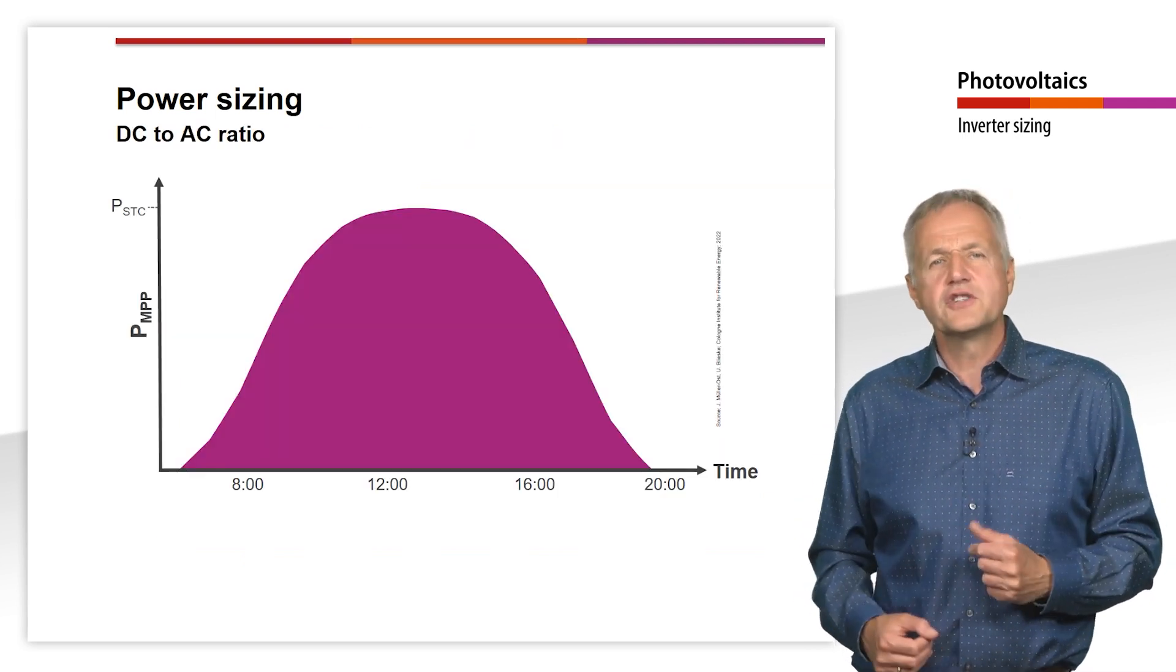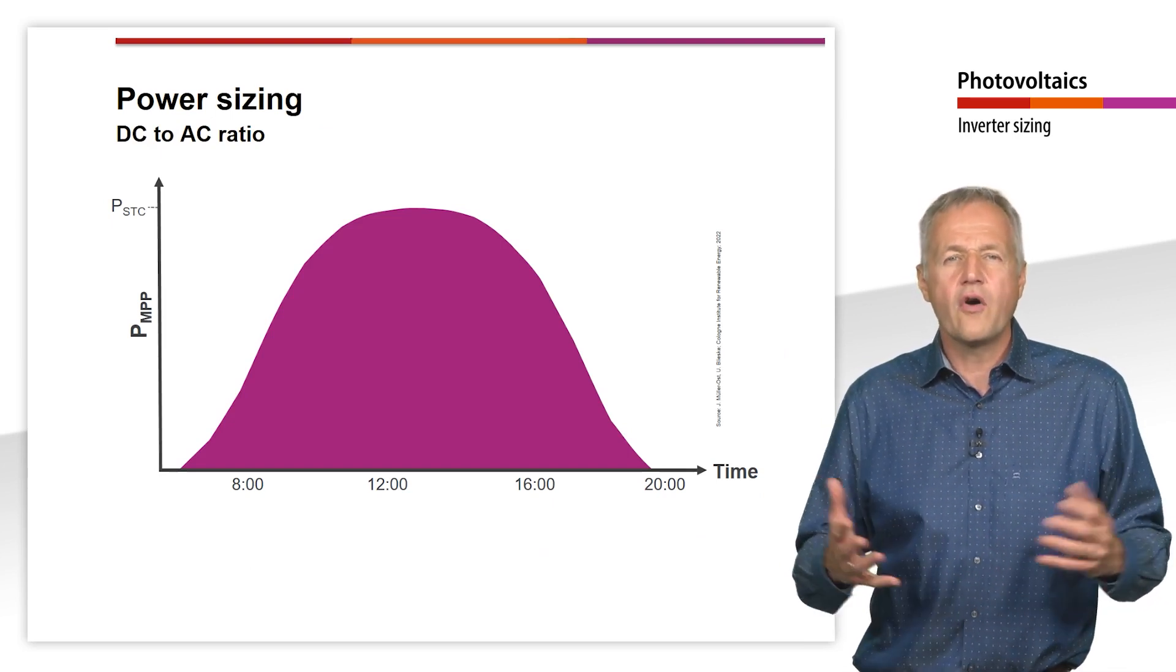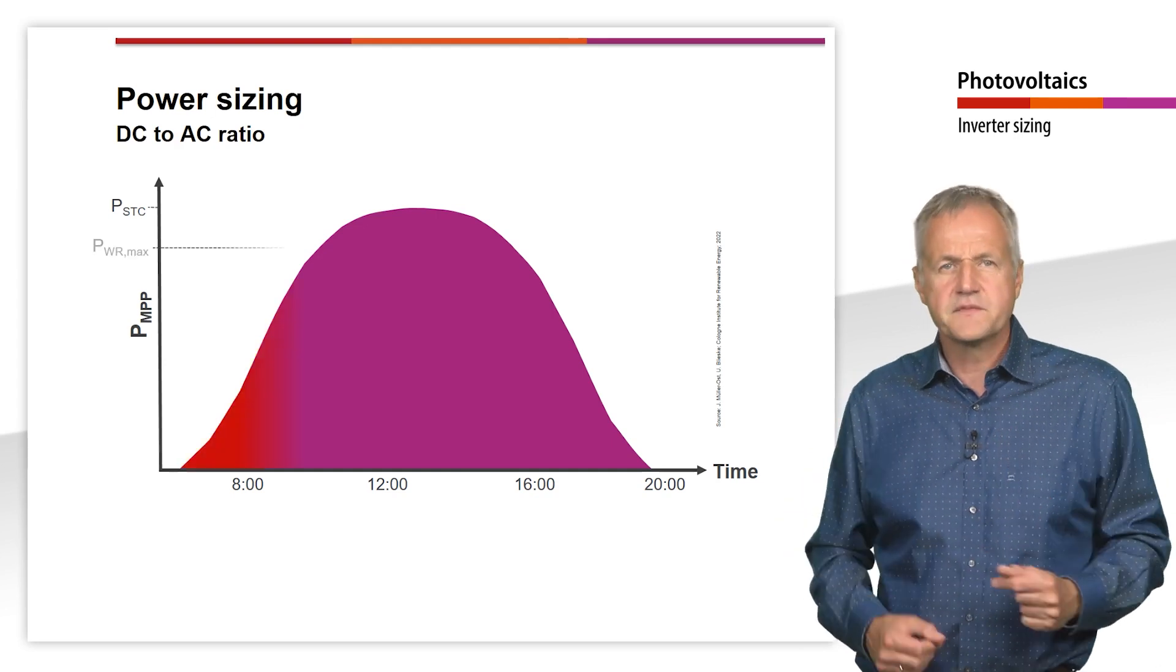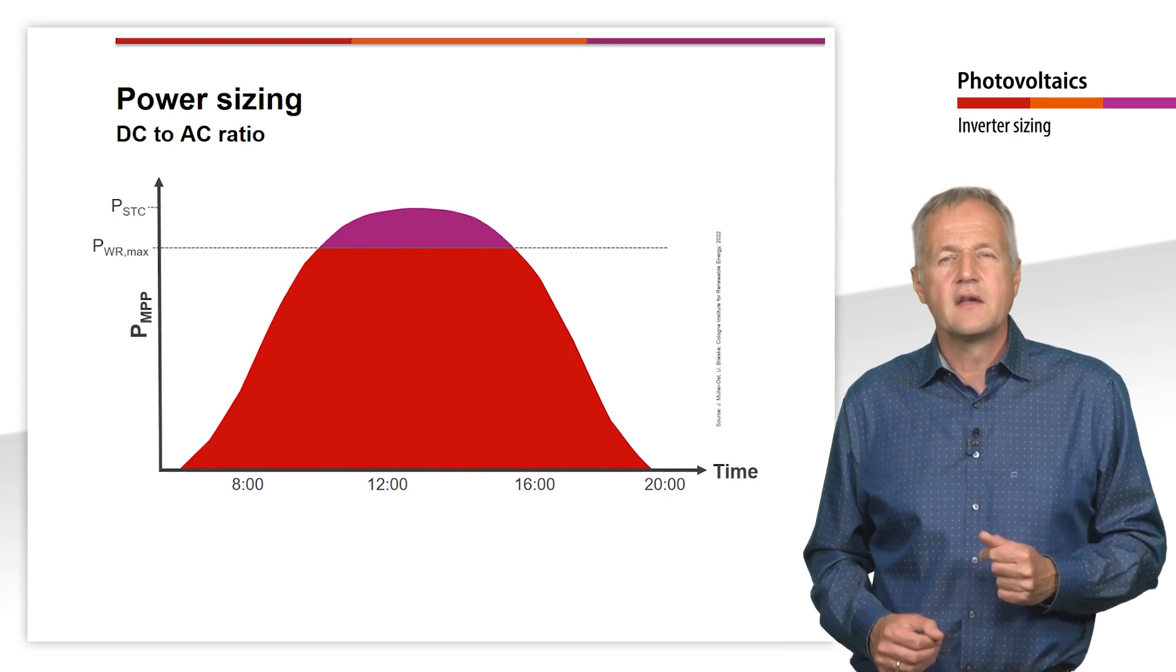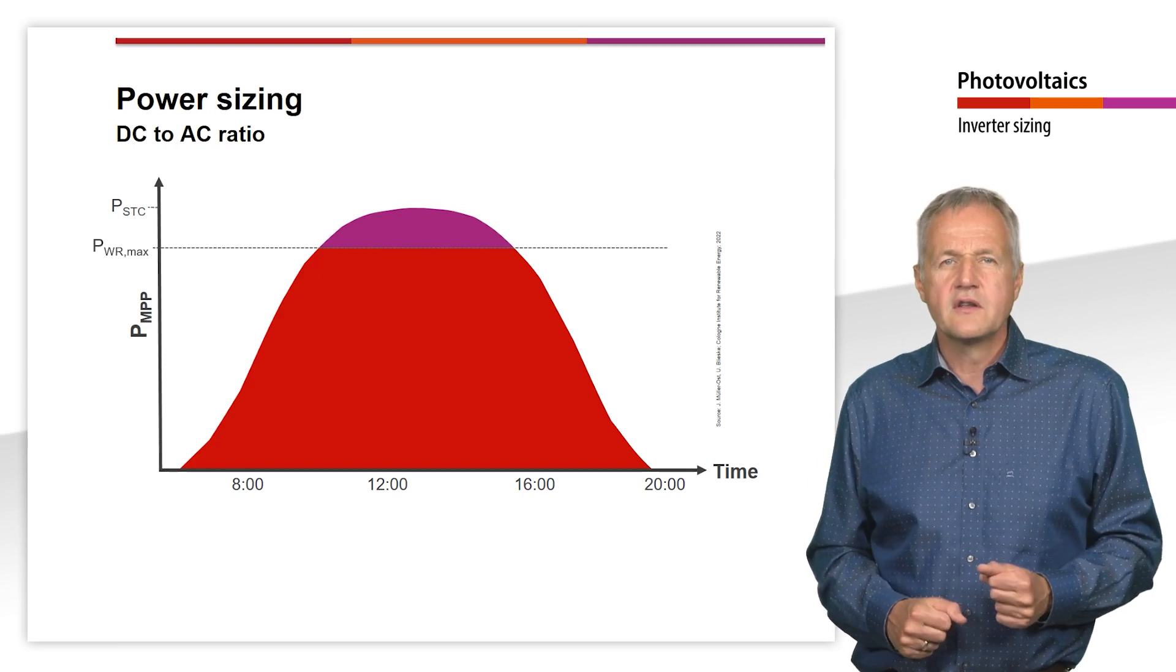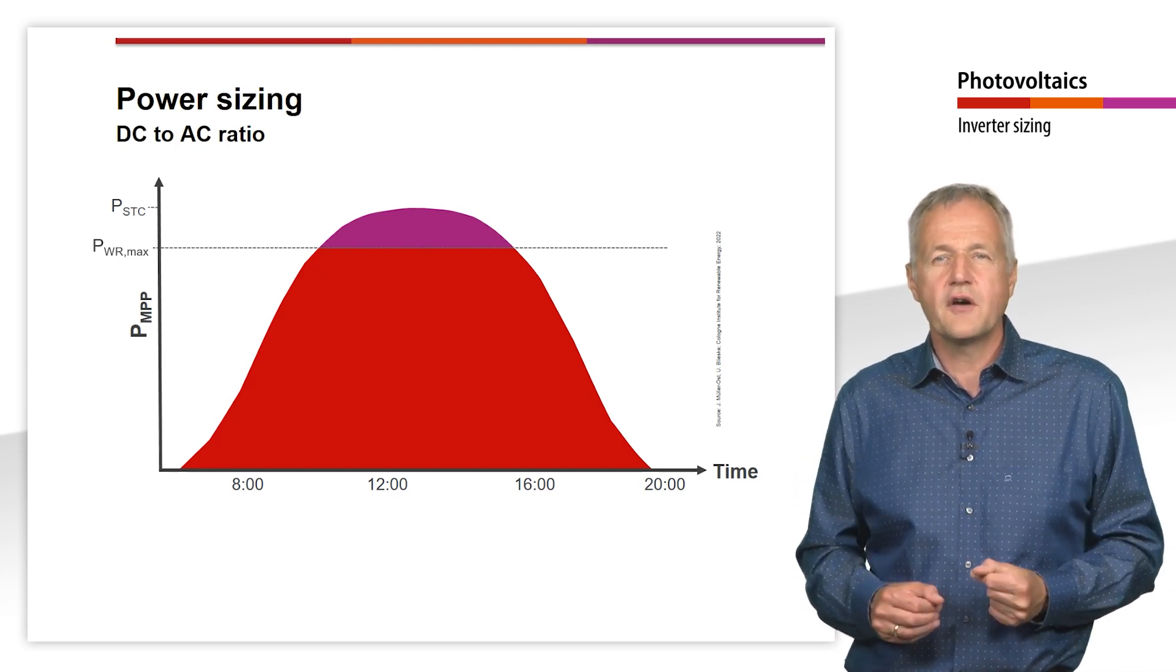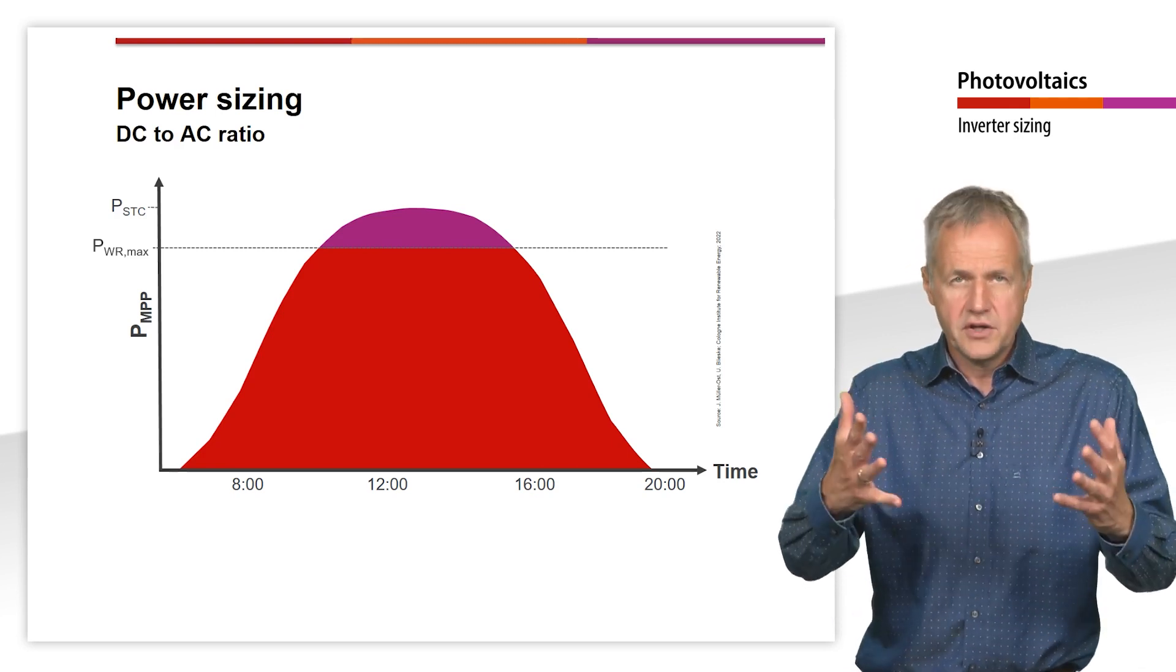You can never destroy the inverter by undersizing it. The inverter will only be loaded more often with its nominal power and the PV power exceeding this will be derated. The inverter does not switch off when the power is too high, but only reduces the output power to its nominal power. This is also referred to as clipping. Clipping causes losses compared to the theoretical possible yield of the PV generator. But the essential part of the energy can be used.